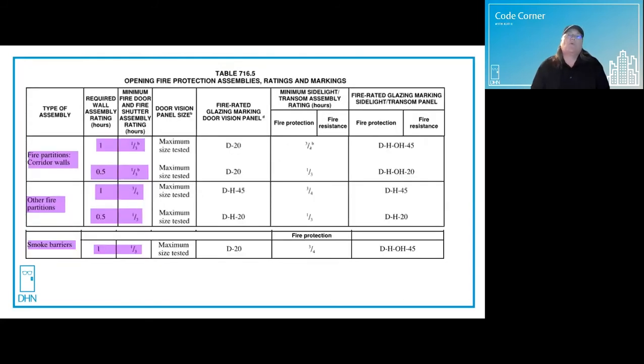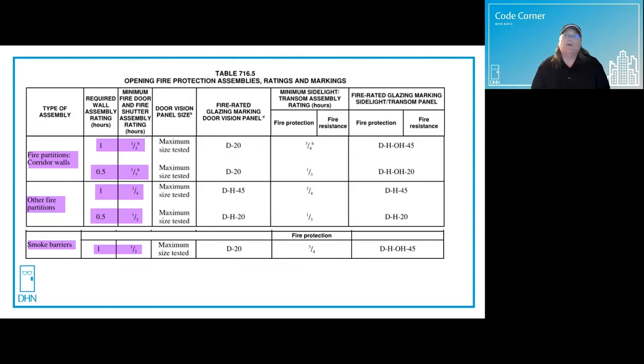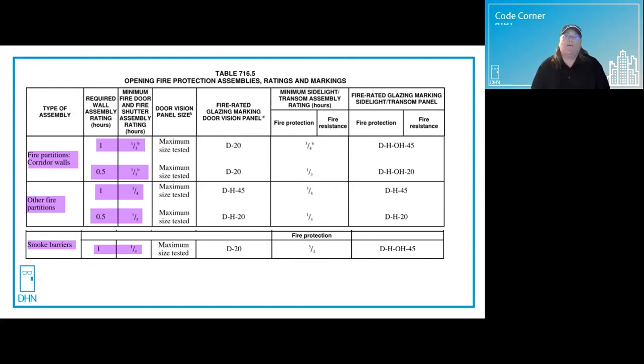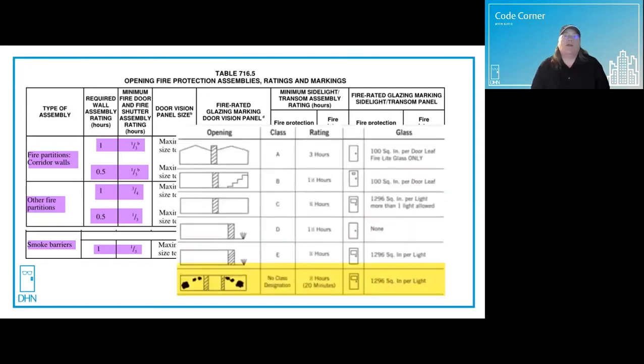Fire partitions are wall assemblies that enclose an exit access corridor. They also separate elevator lobbies. Smoke barriers are used to create smoke compartments in large buildings, and you see them in hospitals a lot more than anywhere else. The doors are required to be one third hour, also known as 20 minute doors. While their primary function is to slow the passage of smoke, make no mistake about it, they are fire doors too.